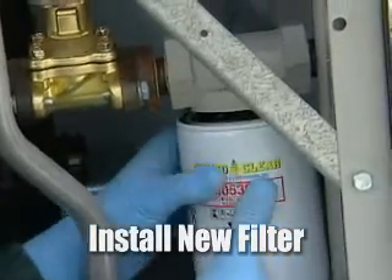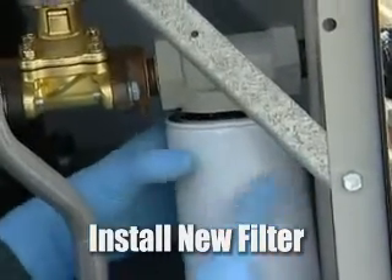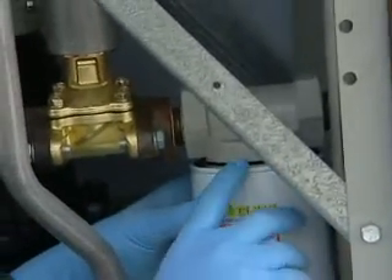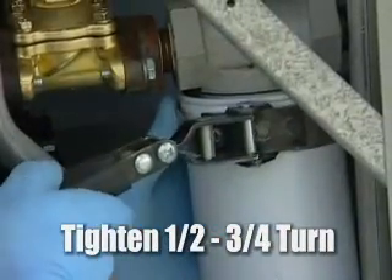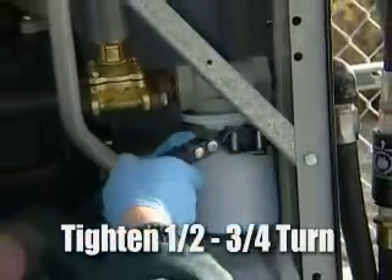It's most important that when the seal actually touches the housing, at that point we need to give it at least a half to three-quarter turns on the filter, so we're not stressing or cracking the filter itself.